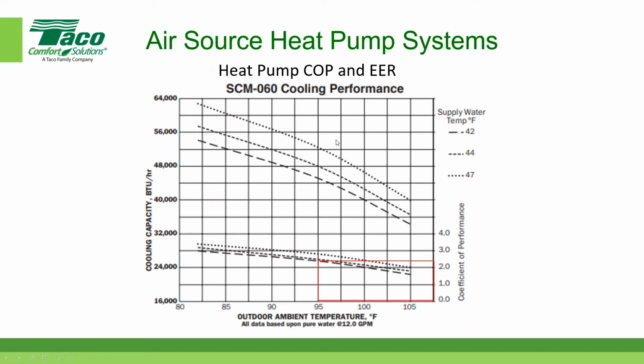This little graph represents the same thing that we saw in the chart. I want to show you that for an ambient temperature of 95 degrees, we had this dashed line here, that meant that we needed 42 Fahrenheit water. At 95 degrees and 42 Fahrenheit water, we go to the right and it shows a COP. Remember we calculated 2.4. You can see that 2.5 would be just above that, so I've estimated that and called it 2.4. Graphically, as the ambient temperature begins to increase, the COP begins to decrease. So if we were trying to make 42 water with 105 ambient temperature, our COP would be maybe around 1.6, in that order of magnitude.